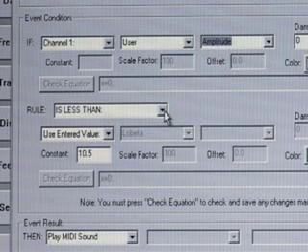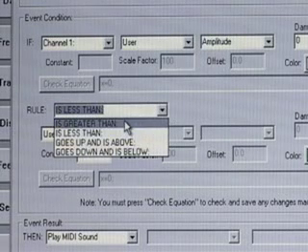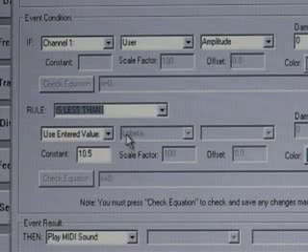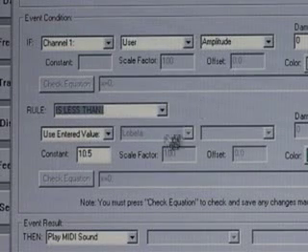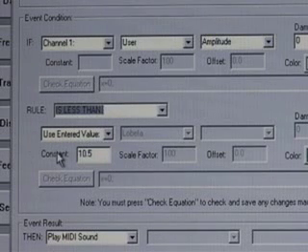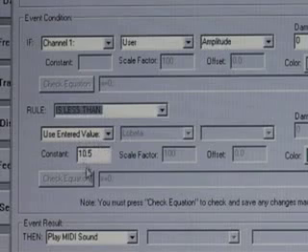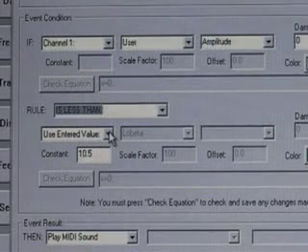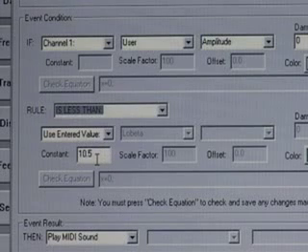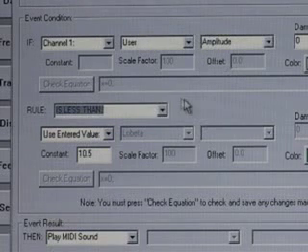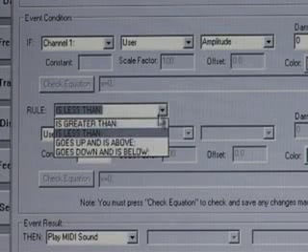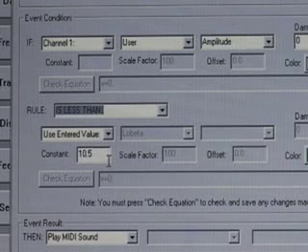Then there's a rule. In this case the rule is 'is less than' because we're doing down training. The rules include: is greater than, is less than, goes up and is above, or goes down and is below. We're going to stay with 'is less than.' The second set of values in the event wizard is called the comparison area. Right now we're saying 'use entered value' and we're giving a value of 10.5. So quite simply, we're seeing if the channel 1 user amplitude is less than an entered value of 10.5.